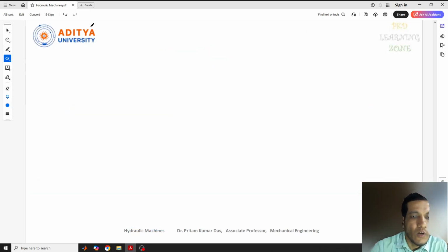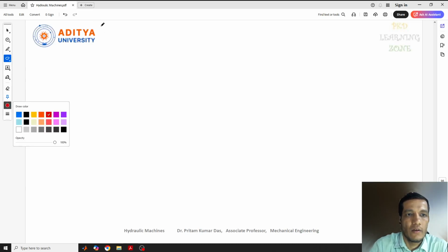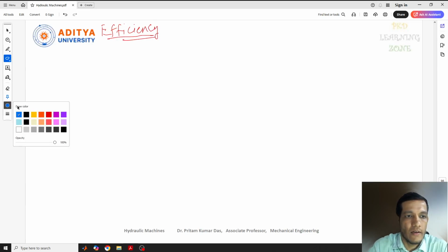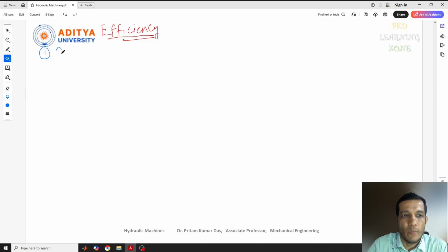For the efficiency, first I'll write manometric efficiency, directly in short form. Manometric efficiency is the ratio of the manometric head to the head imparted by the impeller to the water.